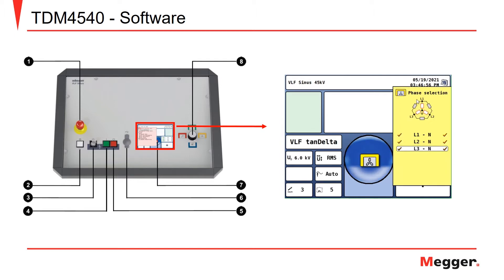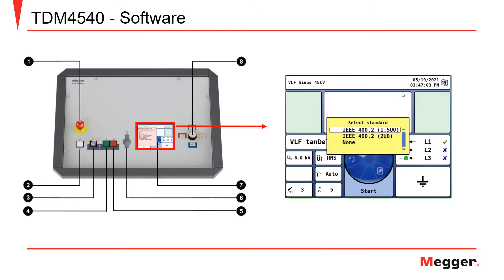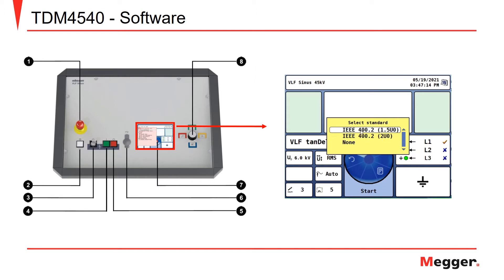Now we have our phase selection, in which we can choose what phase we would like to test. For the purpose of this video, we will choose phase one. Now we can select our standard we'd like to test to, the IEEE 400.2, whether we'd like to go up to 1.5 U-naught or 2 times U-naught. Let's just choose 1.5.